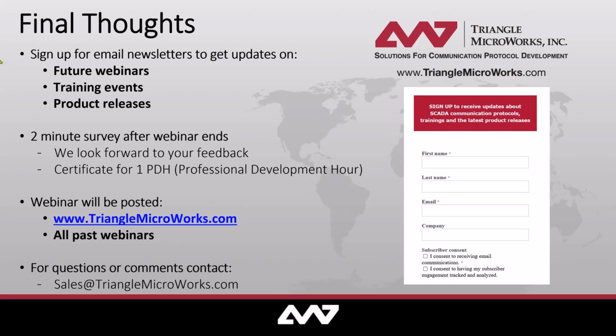You can provide an SCL file, such as an ICD file or SCD file, as we saw today during the demonstration, to give the model that 61850 supports to our SCADA Data Gateway. From there, it's just like the mapping Jackson did today—you grab points from things like your DNP3 or Modbus databases and add them to the model, linking them to a data attribute or data object. We even saw a bit of this when talking about controls. That's how you normally integrate between the two different kinds of protocol models: one being model-based, like 61850 or TASE.2, and the other being DNP3, Modbus, 101, 104, etc.